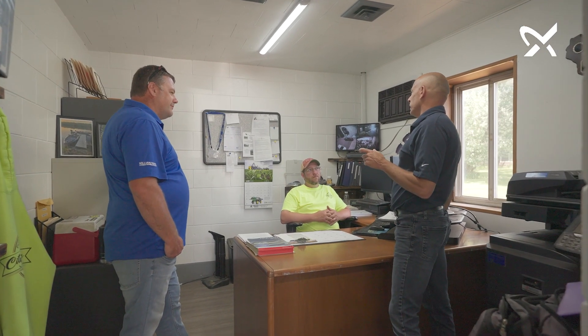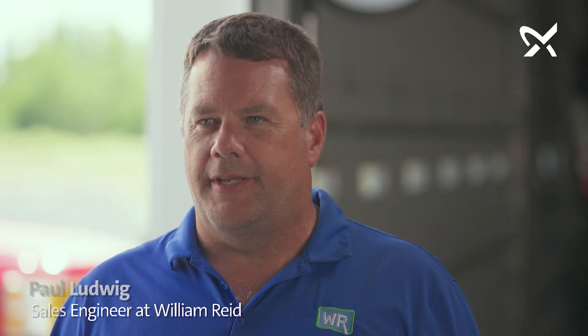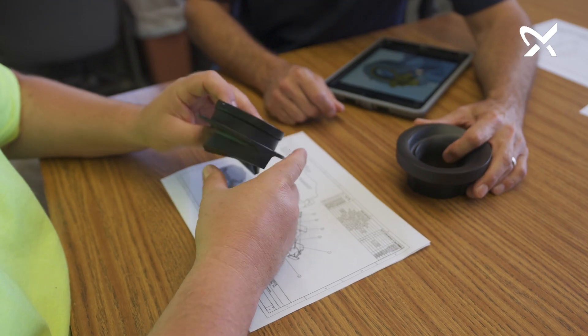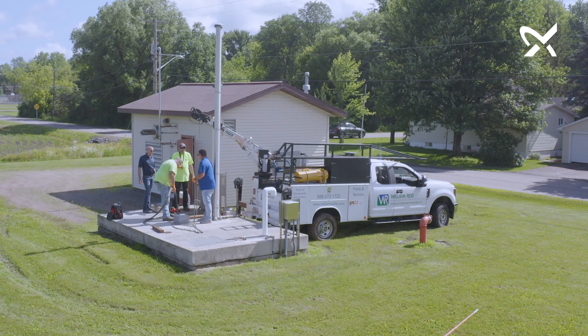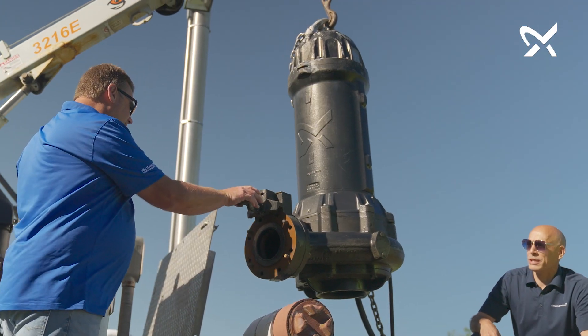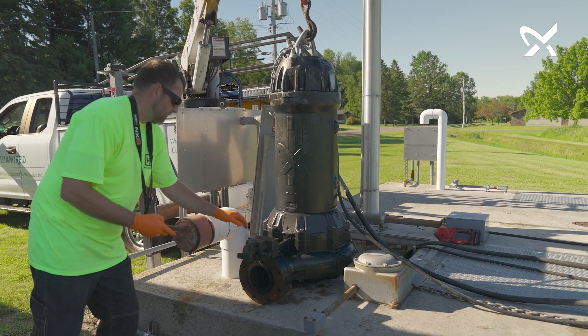Our channel partner, William Reed, came in and asked us for a selection, so we had the opportunity to retrofit and help them solve their challenges at this particular station. The Grundfos pump was selected for this project due to its availability, and the open S-tube impeller was going to help prevent future issues with clogging. The Grundfos selection was unique in the way that it was able to go down the existing guide rails and fit inside where the old pump was, and no modifications were needed to be made to the controls or the base elbows.